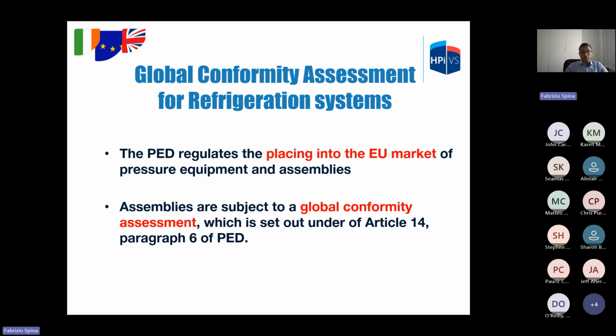The PED regulates the placing into the EU market of pressure equipment and assemblies. A product is placed on the market when it is made available for the first time on the Union market. Each product can only be placed once on the Union market. Assemblies are subject to a global conformity assessment. So when a system is manufactured to be sold in the EU, it must be assessed and certified according to PED. Once it is placed on the market, national regulations apply.